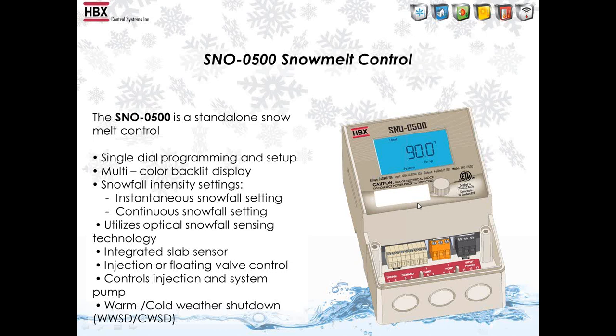So single dial operation, multicolor backlit display. One thing I will tell you is that this is going to be changing probably in the next 3 months. We're going to a new style control, and I'll show you that at the end of the slides. So it has all the same features on it as Snow-1000, the snowfall intensity setting. So we have the instantaneous snowfall setting, the continuous snowfall setting. Obviously it uses the optical snow technology. Integrated slab sensor is also still built into that SNO-0500. You can have injection mixing or floating action mixing, warm weather shutdown, cold weather shutdown. So it has all of the features that you need for your basic snow melt systems that 99% of people are putting in now.